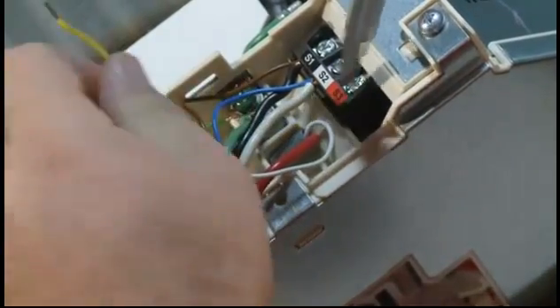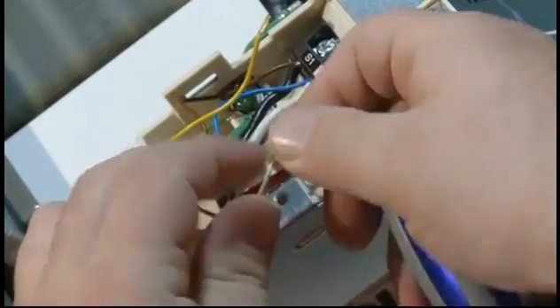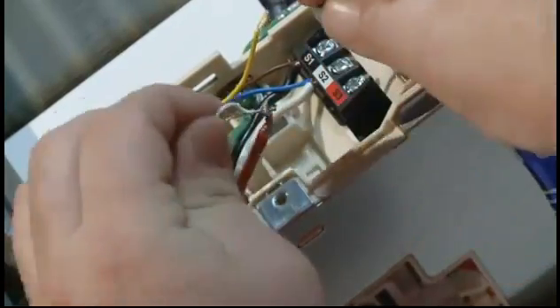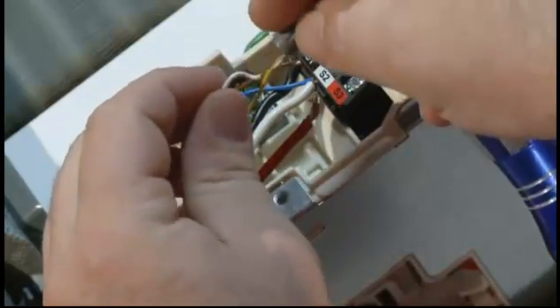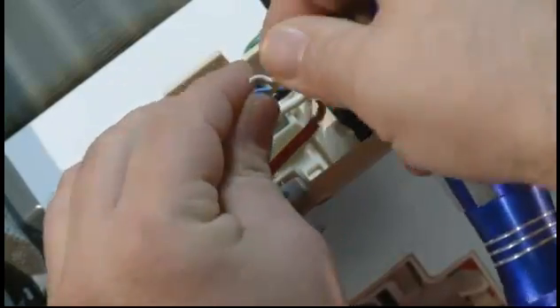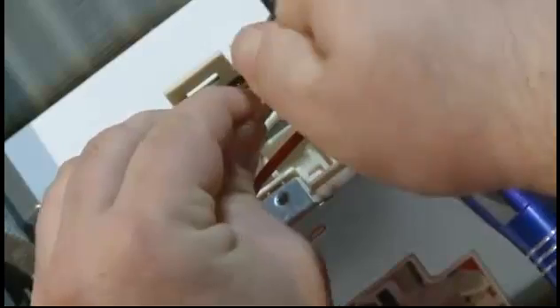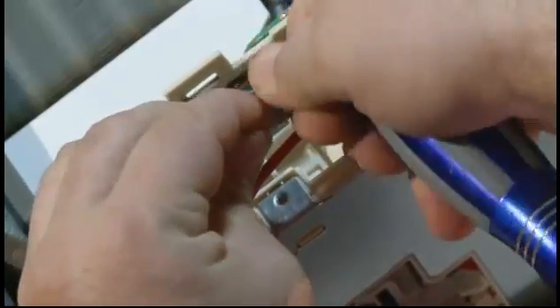Condensate pumps are the number one cause for this, along with junction boxes with loose wire nuts, or just having a cut wire. If the condensate pump is wired to break the S3 wire for safety, it could be your condensate pump not pumping, which is causing your communication error.